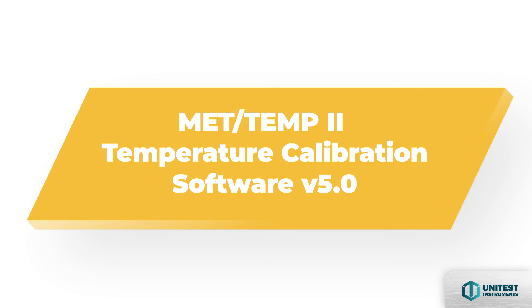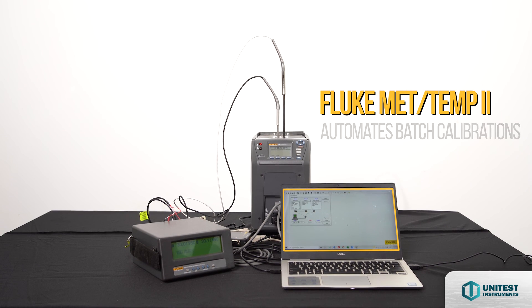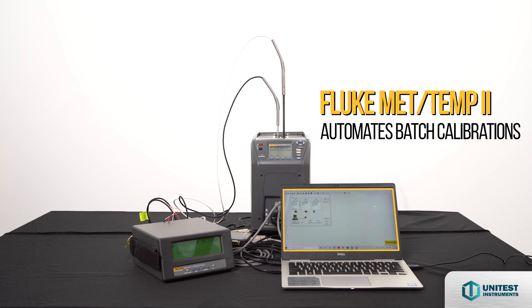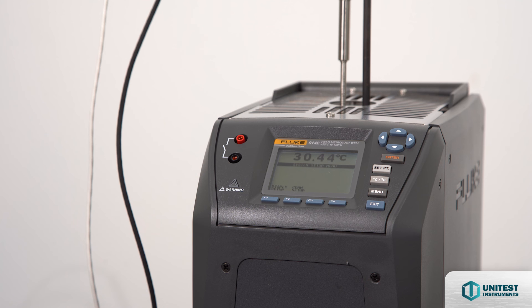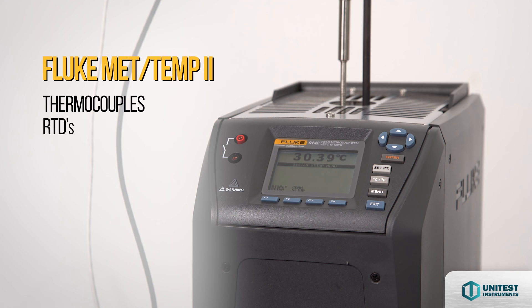Introducing MET/TEMP II temperature calibration software version 5.0. MET/TEMP II fully automates batch calibrations of your platinum resistance thermometers, thermistors, and thermocouple sensors, freeing your time for more important tasks. MET/TEMP II handles a wide range of temperature sensors — it can calibrate thermocouples, RTDs, SPRTs, thermistors, liquid-in-glass and bimetallic thermometers, and connected sensors that can't be attached to a readout. It provides a comprehensive temperature calibration solution for testing batches of sensors, calculating characterization coefficients, and printing calibration reports.